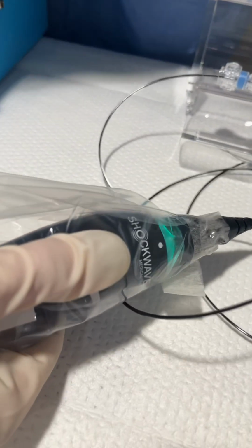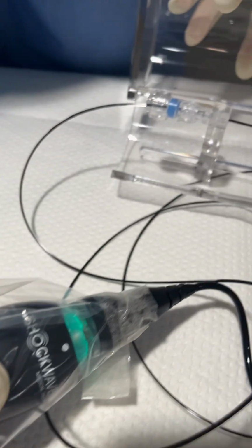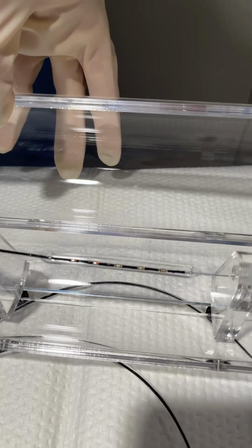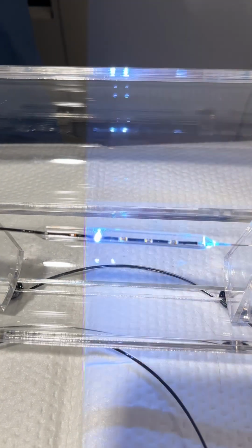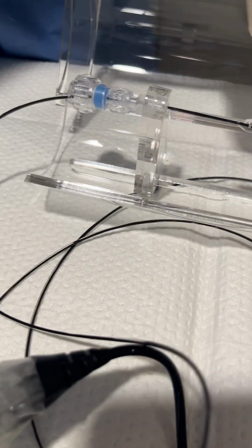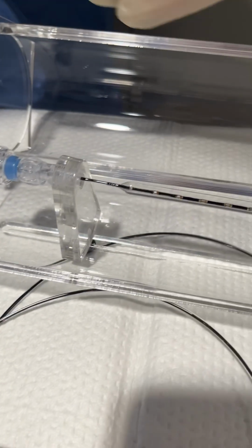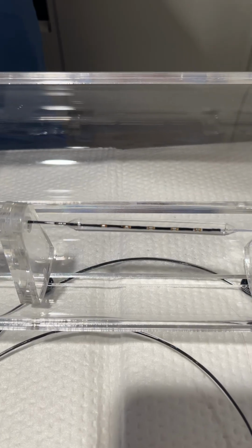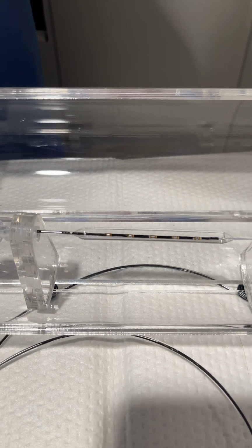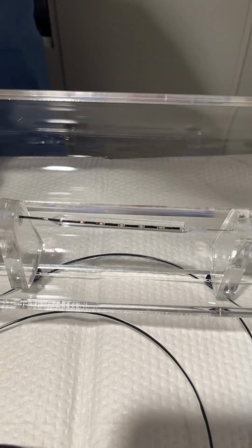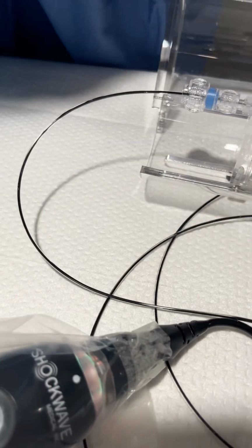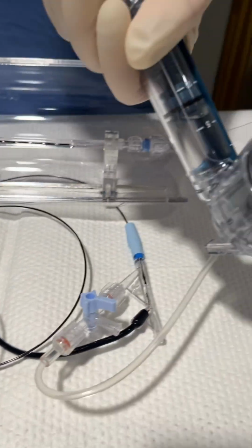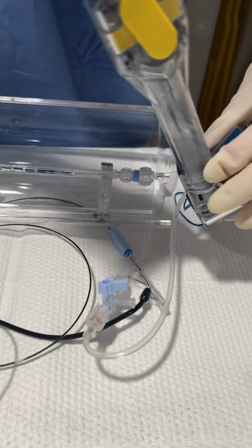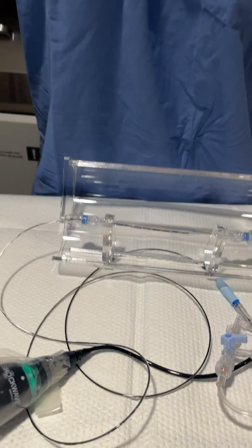Green means go. We then hold your thumb on the cable, the pulse button, and we deliver therapy. Each pulse is starting at the generator, traveling through the connector cable and exiting at these emitters. Once it exits at the emitters, it converts into acoustic sound waves that are measured at 50 atmospheres of pressure. At the pause, you'll see a yellow indicator to then go up to 6 atmospheres and come down. And that is one treatment on the M5 Plus.